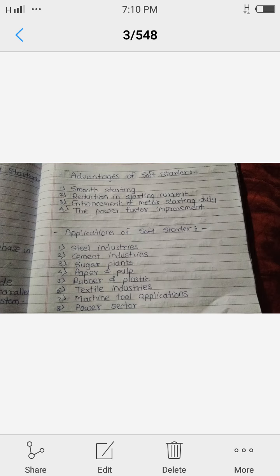Soft stop. Soft starters can have soft stop included for no extra cost. Soft stop is the opposite of soft start. The voltage is gradually reduced, reducing the torque capacity of the motor. The reduction of available torque causes the motor to begin to decelerate when the shaft torque of the motor is less than the torque that is required by the load.